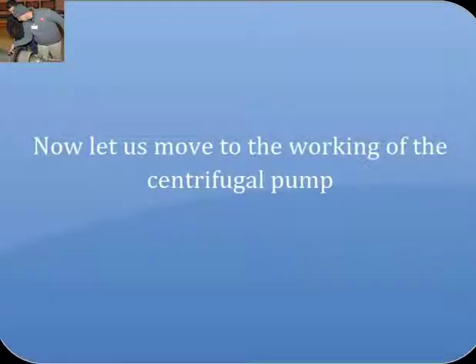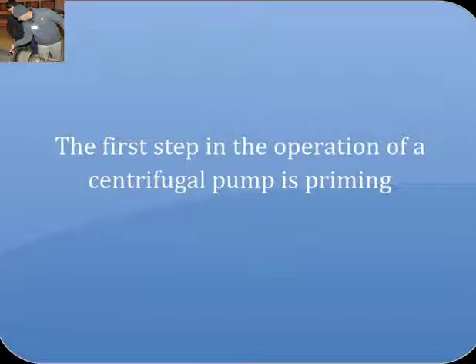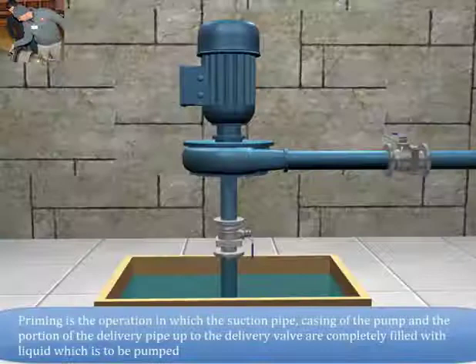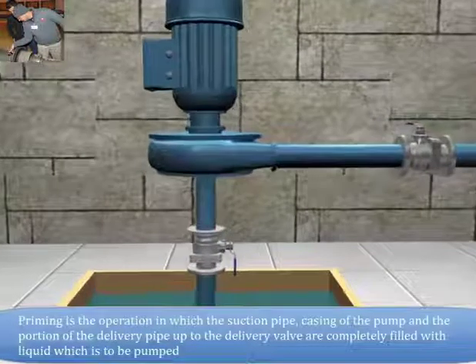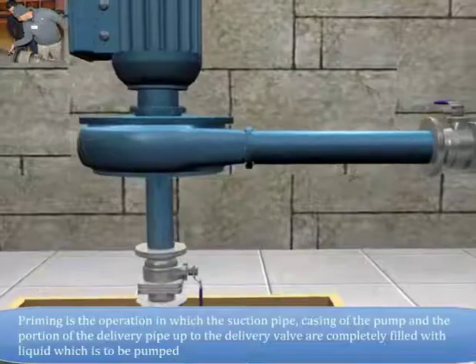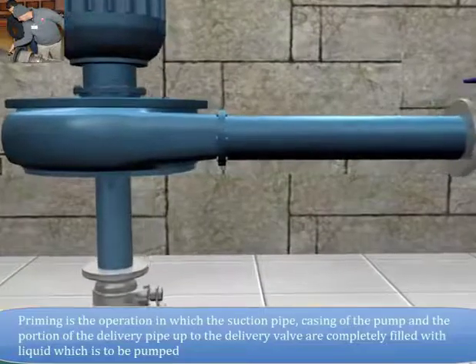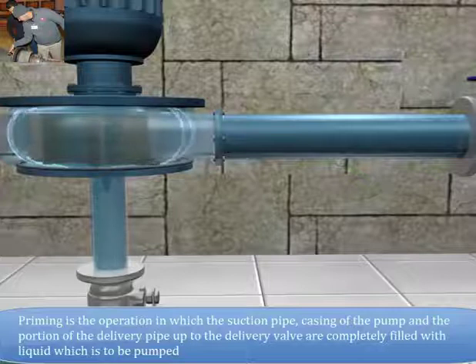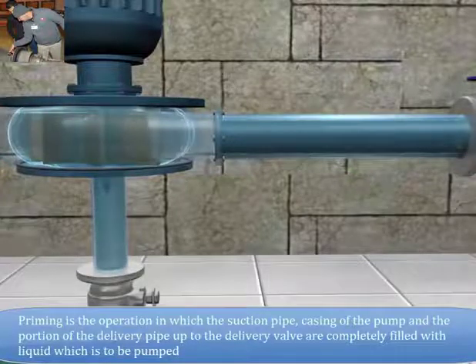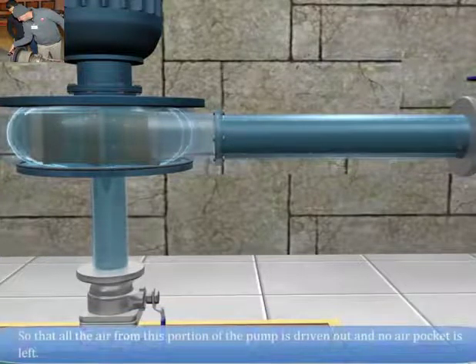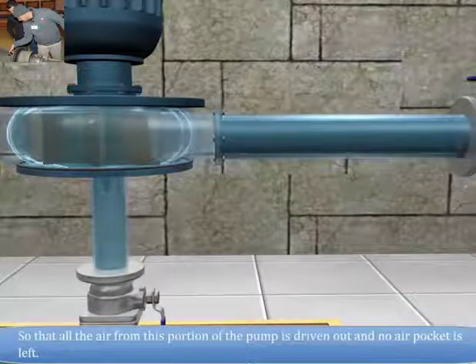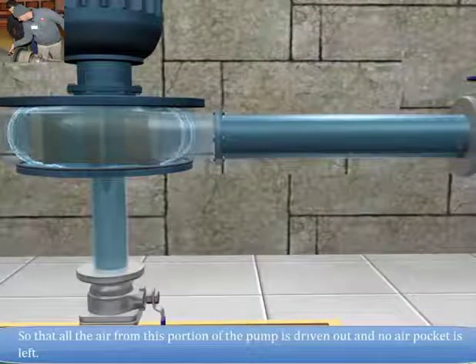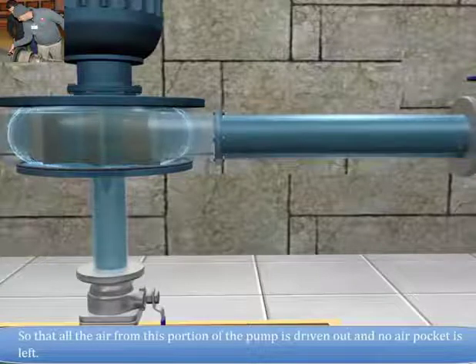Now let us move to the working of the centrifugal pump. The first step in the operation of a centrifugal pump is priming. Priming is the operation in which the suction pipe, casing of the pump and the portion of the delivery pipe up to the delivery valve are completely filled with liquid which is to be pumped, so that all the air from this portion of the pump is driven out and no air pocket is left.